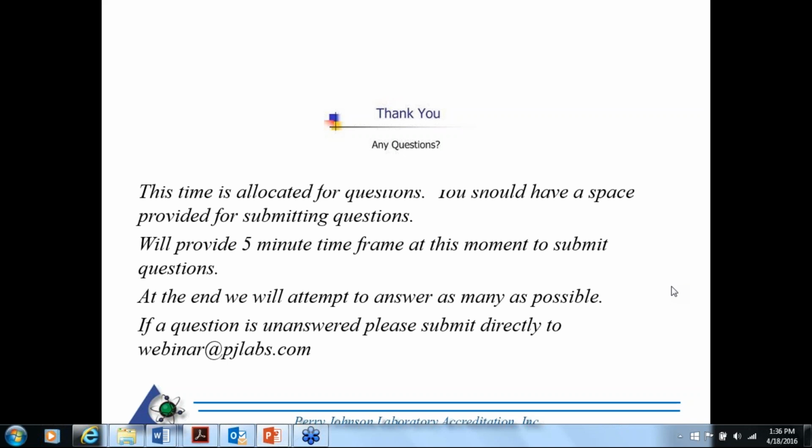I'm not sure I'm really clear on the question of does every piece of equipment calibrated need test data? Well, in the realm of Section 5.10, you are required to report the actual calibration results, including the units of measure.